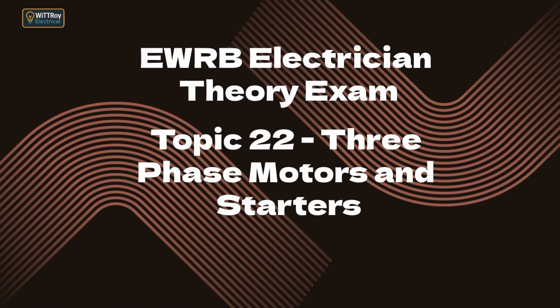Topic 22.2a. Explain the principles of operation of a three-phase induction motor in terms of the stator rotating field, rotor currents and flux, relative motion between the rotating field and rotor and the direction of rotor rotation. A three-phase induction motor works because of a rotating magnetic field produced by the stator windings. Here's the sequence. 1. Stator rotating magnetic field. A three-phase supply feeds the stator windings. The three currents are 120 degrees apart. This creates a magnetic field that rotates smoothly around the stator. The speed of this rotating field is called synchronous speed.